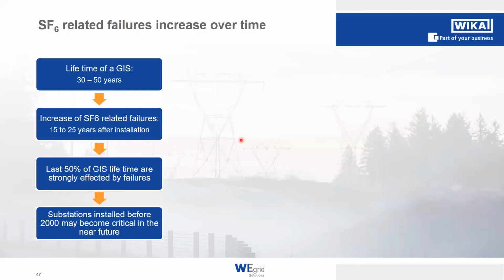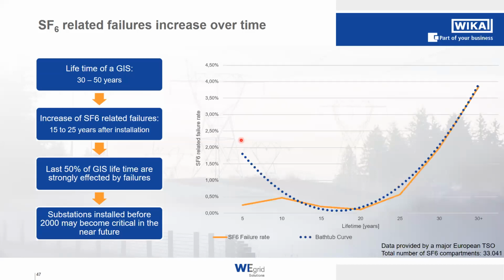And as it is 2020 today, switchgears that have been installed before 2000, so in the 1900s, they might become critical in the near future. So SF6 related failures increase over time, and that's what we also see in this graph on the right-hand side. This is a GIS failure rate analysis of a European TSO, the information that we received for over 33,000 SF6 gas compartments.